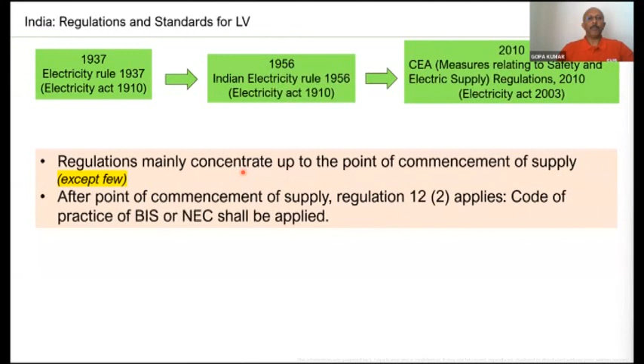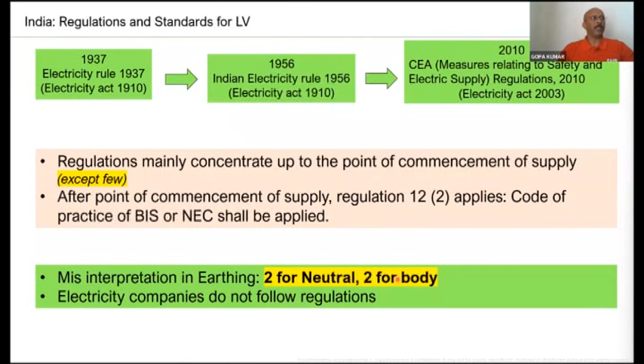Here, once it comes to practice, the first and foremost mistake - I always laugh at this - is '2 for neutral, 2 for body.' Earthing: transformer, 2 body, 2 neutral; DG, 2 body, 2 neutral. This is one of the biggest mistakes we make in India. As a result, MCBs won't trip, and finally we end up in trouble - fire or electrocution - because of this misinterpretation, which is common across India.